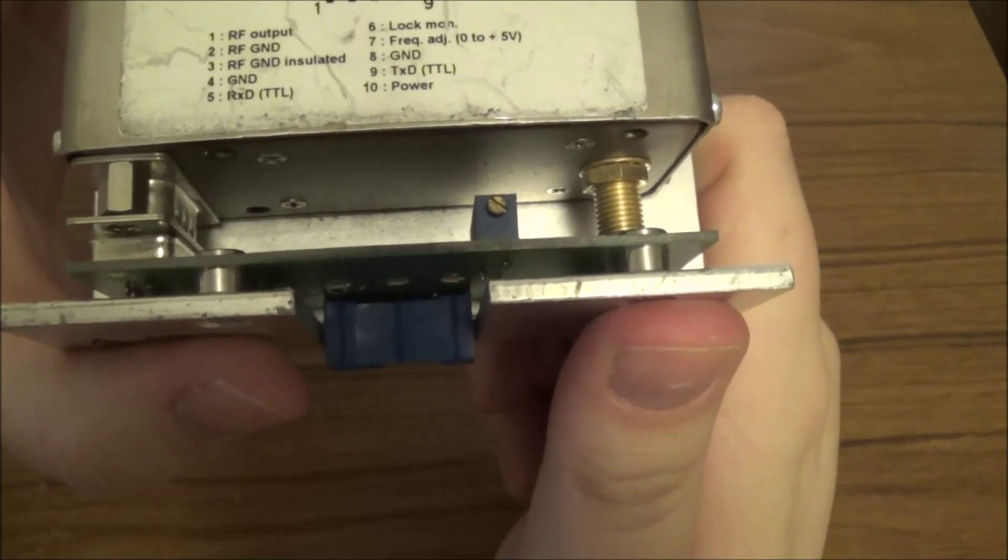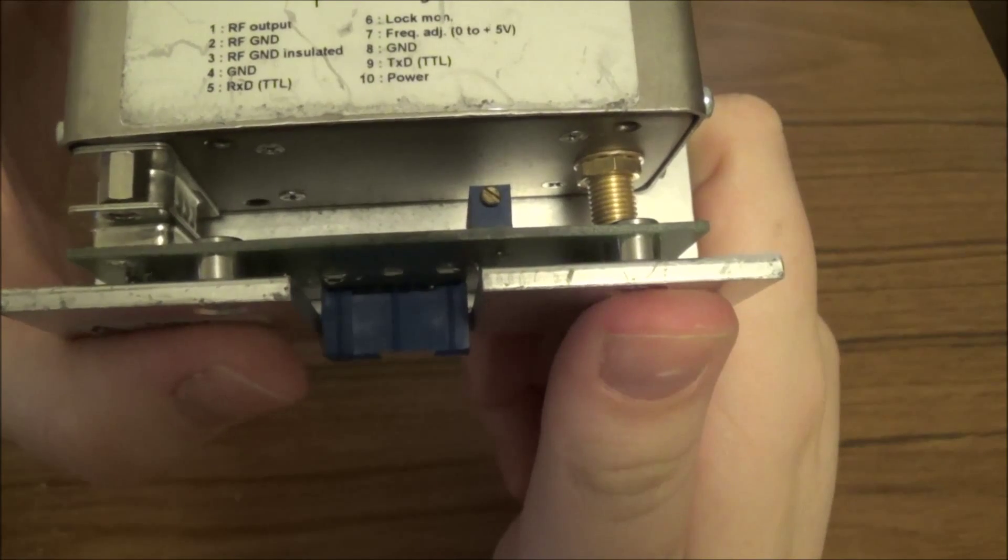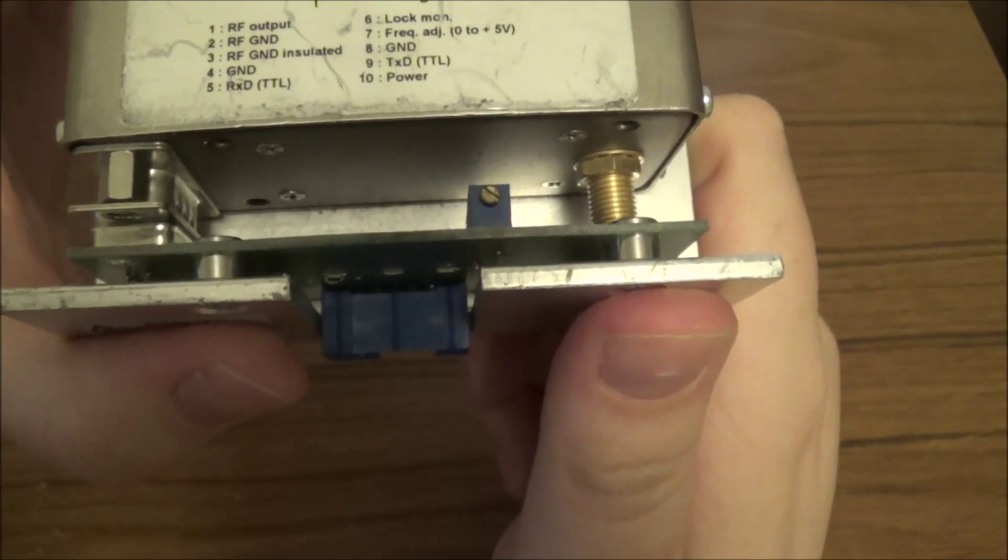The reason for this trim pot is that these rubidium standards aren't inherently accurate. They need to be calibrated against a better timing source like a cesium standard.